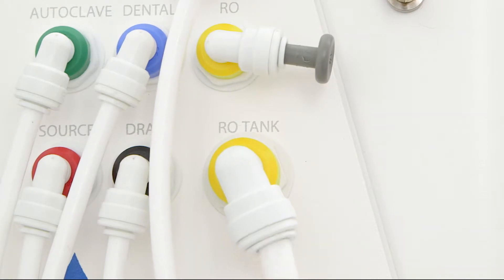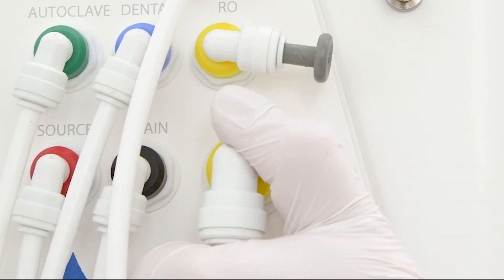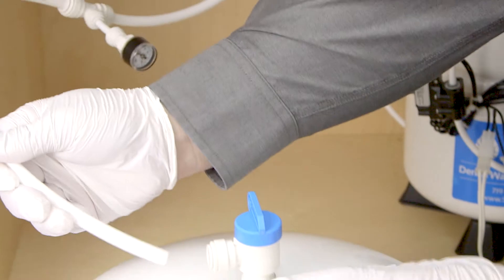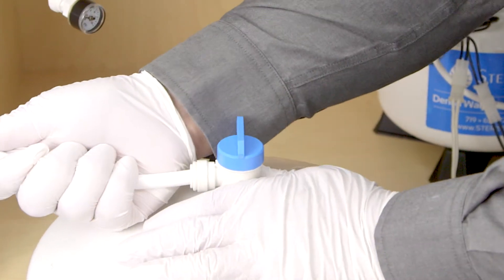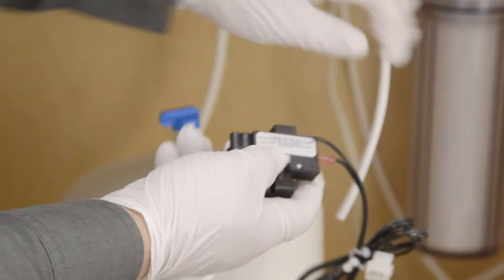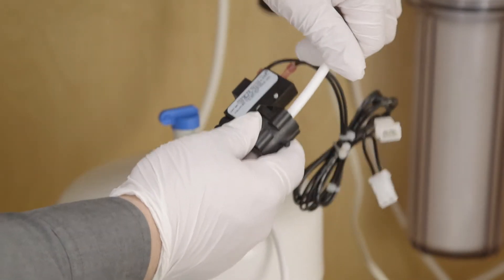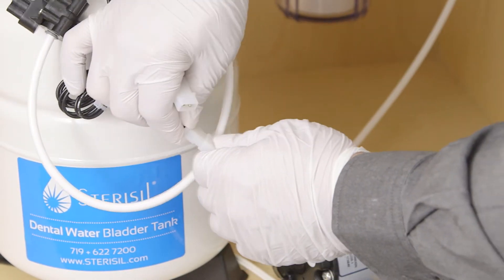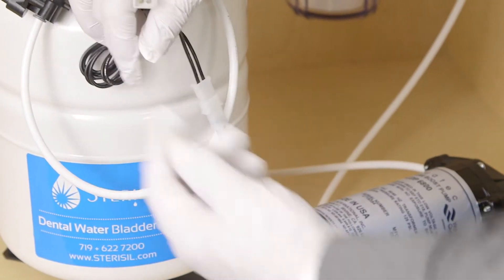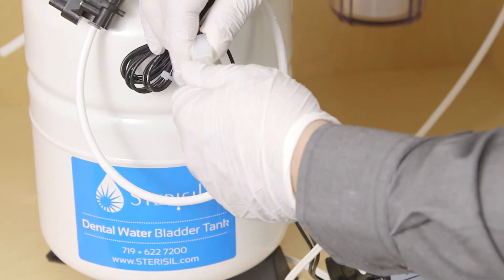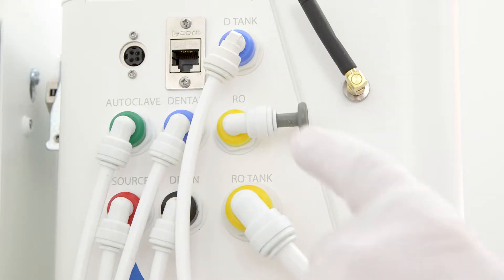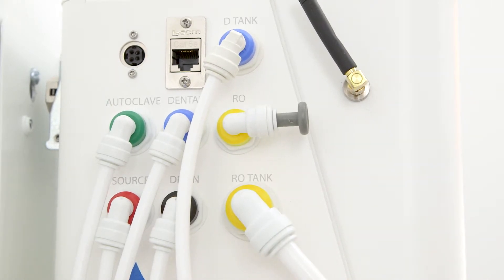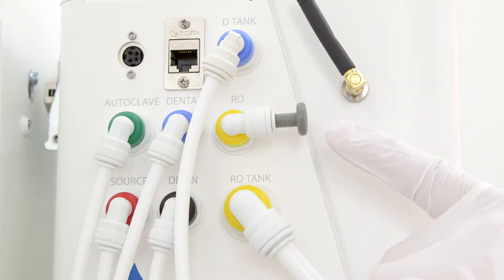RO tank port. Run a three-eighths inch line from the RO tank port on the system to the three-eighths inch tank ball valve on the RO water storage tank. The pressure switch for the booster pump must be installed on this section of tubing. Make sure you have enough length on the power cable to reach between the pump itself and the section of tubing with which you intend to merge the pressure switch. You'll now be left with a yellow RO port. If no auxiliary reverse osmosis water will be used, then this port should remain plugged.